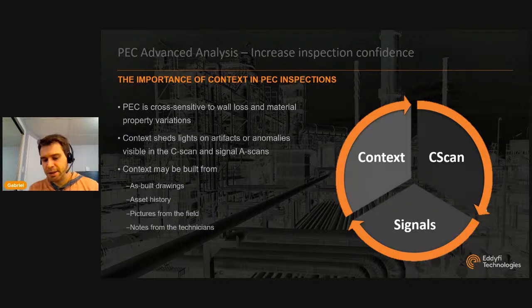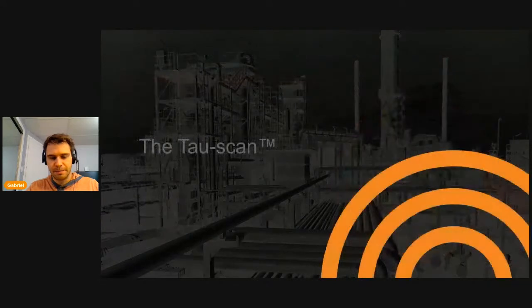And so if you're scanning, say, a pipe, and there is another pipe right above it that's coming perpendicular, and right underneath this area you see an effect on the PEC signals. And if you've got pictures or an understanding of the context, you know that it's that surrounding component that's affecting the PEC signal. Same thing if you scan up against a flange or something like that. So it's really important to have access to the drawings and the asset history, and that helps get a better understanding of what's going on in the signal when you've got feedback or changes that are induced by something other than just wall loss or wall thickness variations.